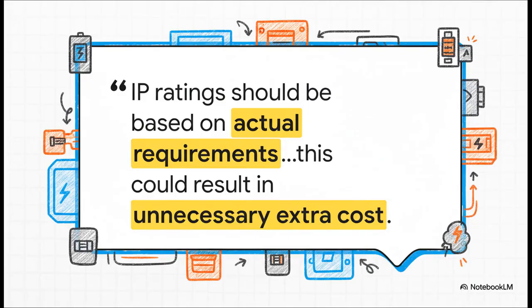But here is a pro tip that can save a project a ton of cash. Don't overspecify the IP rating. Seriously, if your switchgear is going to live in a nice, clean, dry electrical room, it does not need to be built like a submarine. Specifying a higher IP rating than you actually need just jacks up the cost for literally no reason.